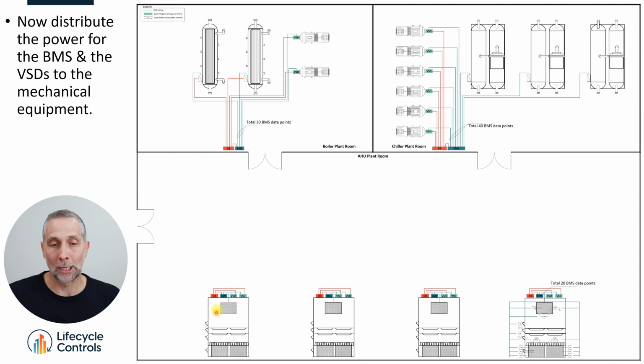And here on the air handling unit, we've got a little mini distribution board, almost a domestic-looking thing. It's got a 3-phase circuit breaker for the supply fan VSD. We've got a 3-phase circuit breaker for the return fan VSD. There's a single-phase circuit breaker for the BMS control panel. You could have a single-phase circuit breaker for the AHU lighting. If you have a runaround pump or a humidifier, there's a single-phase circuit breaker for that as well. So we have distributed all the controls and all the power throughout the plant room and not have centralized systems.